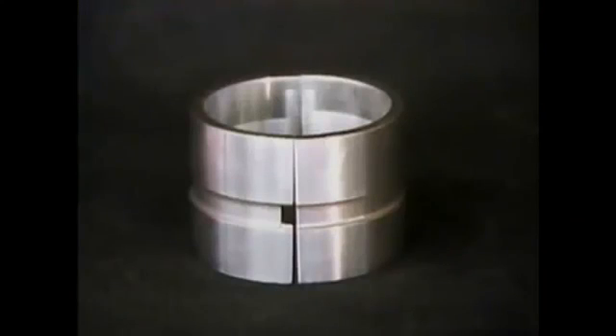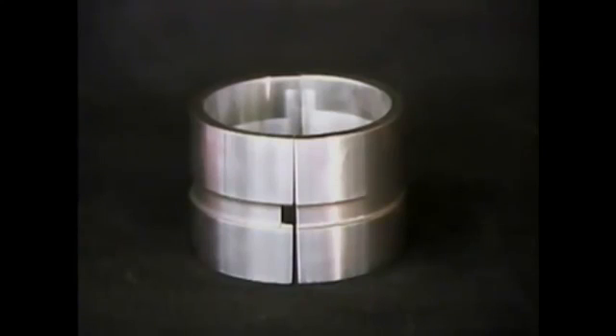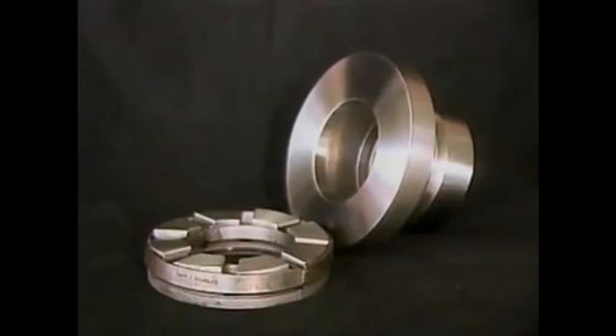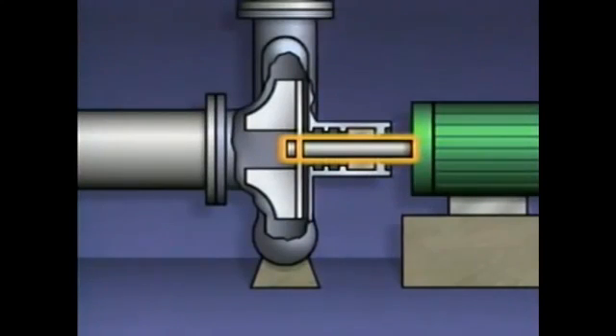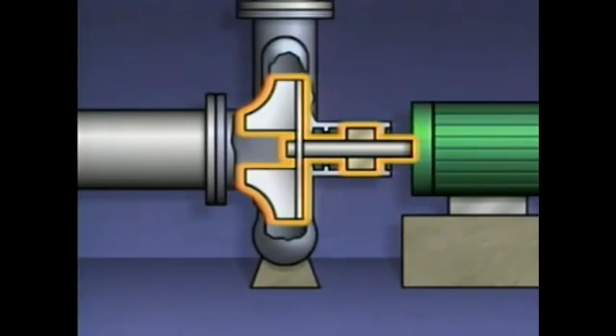The next components we'll look at are bearings. Two types of bearings used by most compressors are radial bearings and thrust bearings. Radial bearings support the compressor shaft and are lubricated to allow the shaft to rotate freely inside the casing, while preventing most radial movement — that is, movement perpendicular to the shaft. Thrust bearings prevent axial movement, which is movement along the axis of the shaft. By allowing the shaft to rotate while keeping it in position, the bearings keep the impellers or blades from hitting the stationary parts and being damaged.